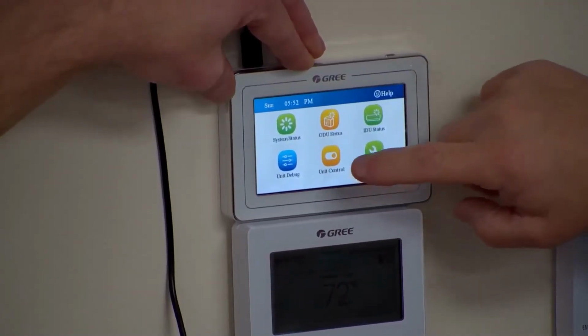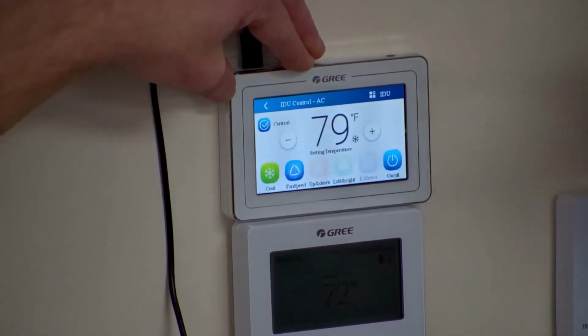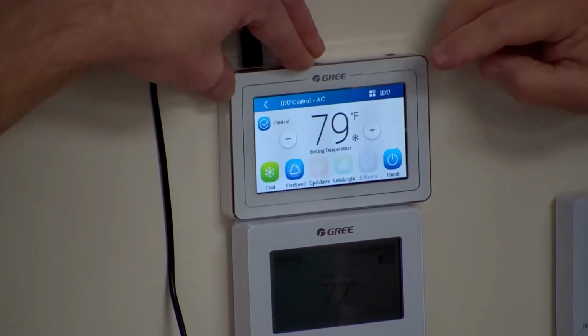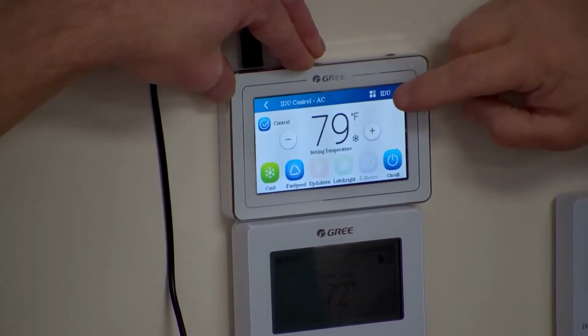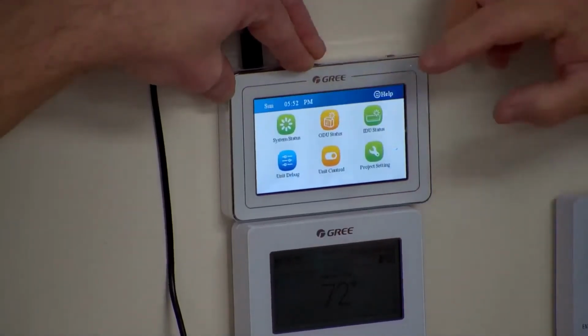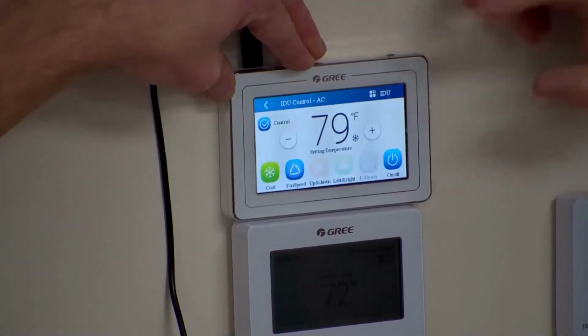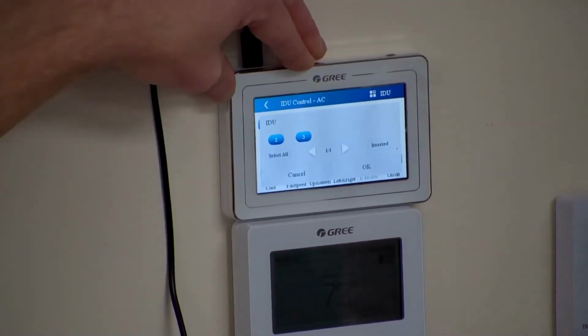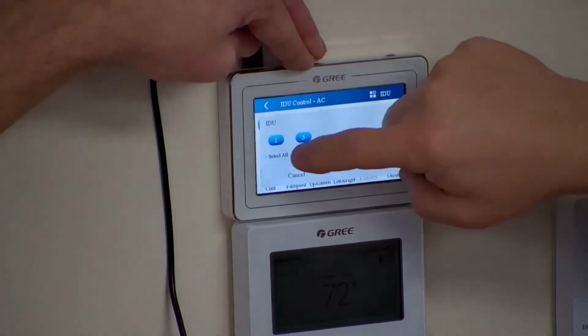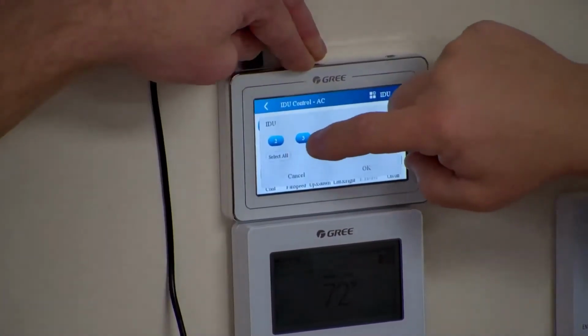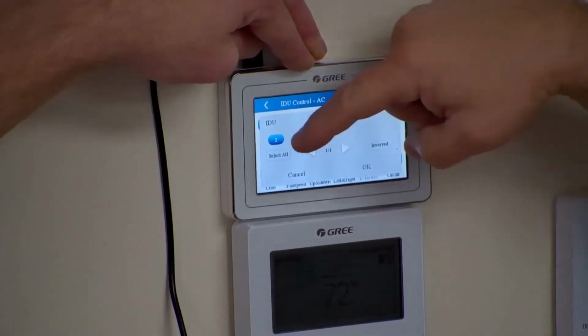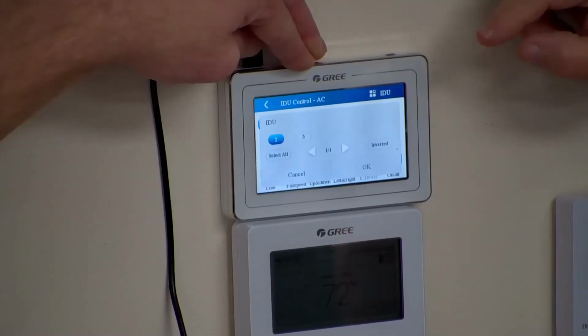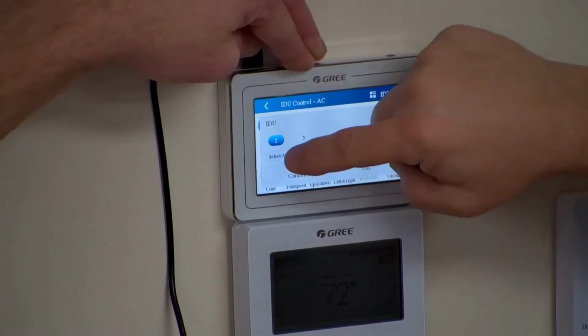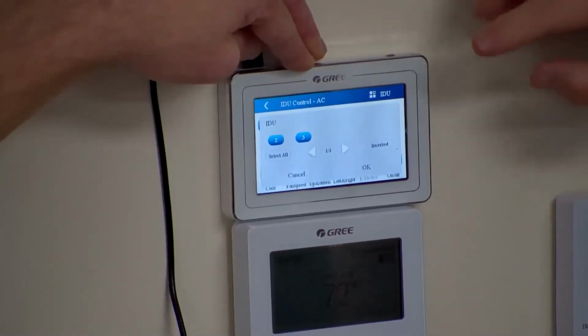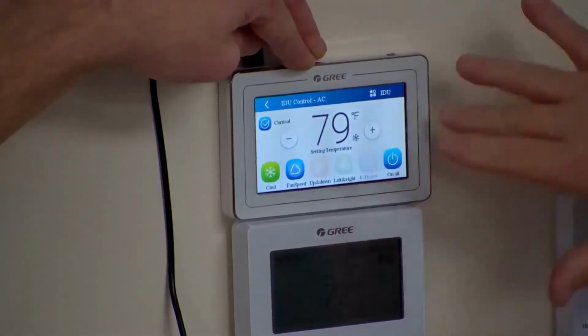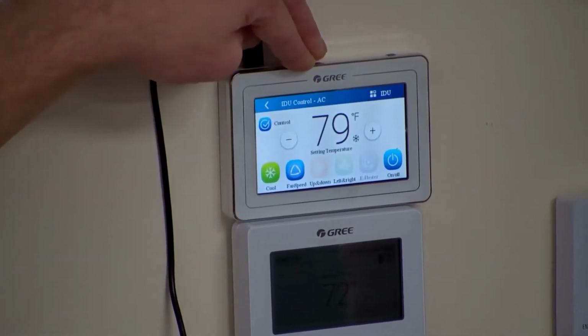So we can check all the sensors, all the EEV steps. If I go to unit control, I can control the entire system from this tool. So now you've got to choose what you're going to drive. You go to unit control, you go indoor unit. As you can see on this system, there's 2 indoor units. I can do select all, or I can just do 1. So you can see right now I'd only be driving unit number 2. I'm not driving 3. But if I do select all again, now you'll see it highlighted both. Now I hit OK. So now I know whatever I do here is sending that command to both units.